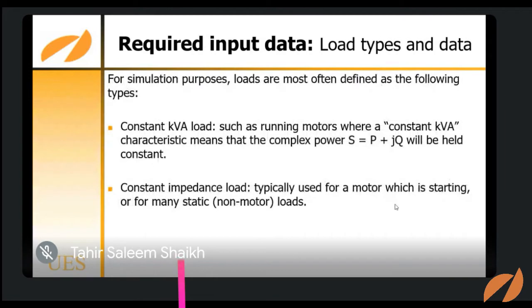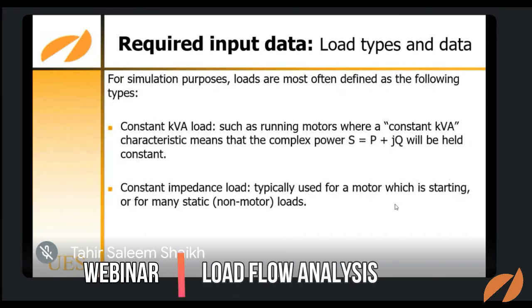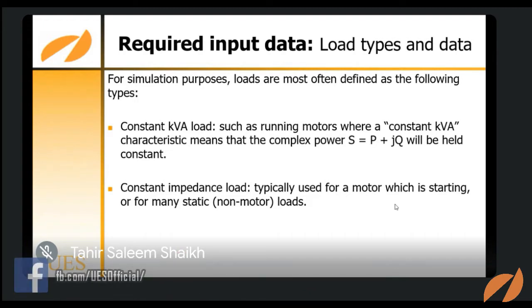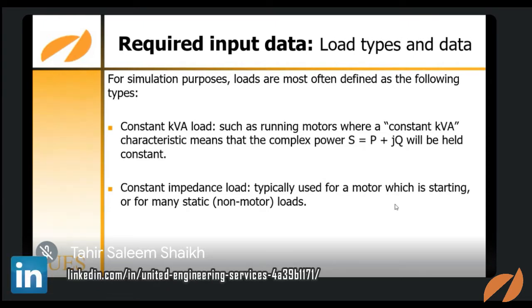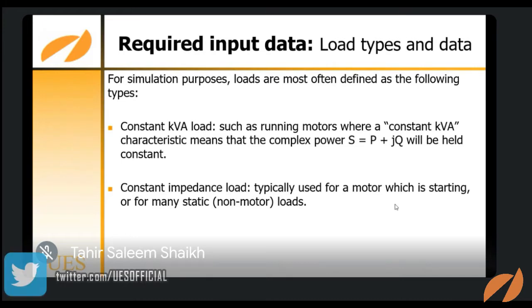Okay, for simulation purposes, loads are often defined as the following types. Now, I'm just going to give you a short review of these kinds of load. In a constant kVA load, the power of that load is predefined, that this amount of power will flow. So this is a constant kVA load. It will not be affected by changes in system parameters, voltage or phase angle, but this constant kVA load will remain the same.